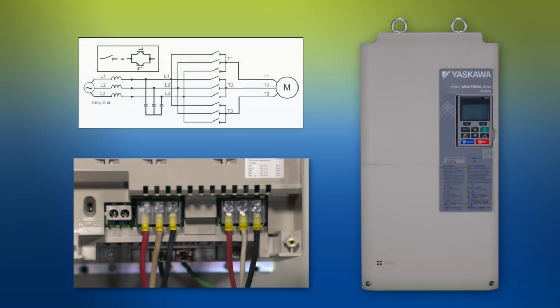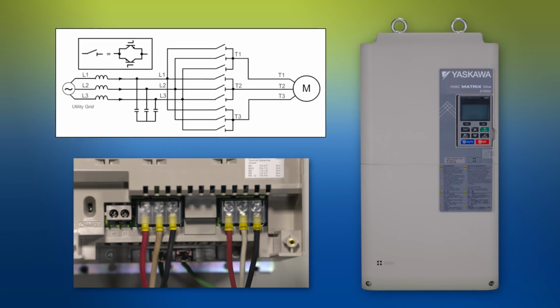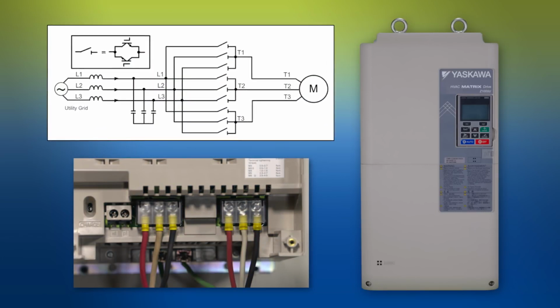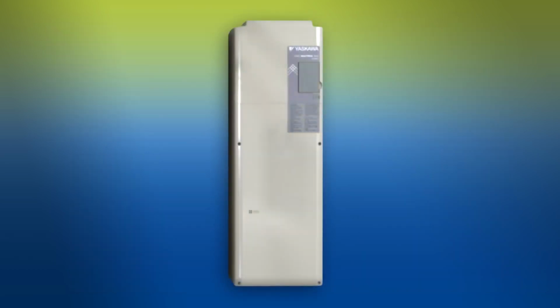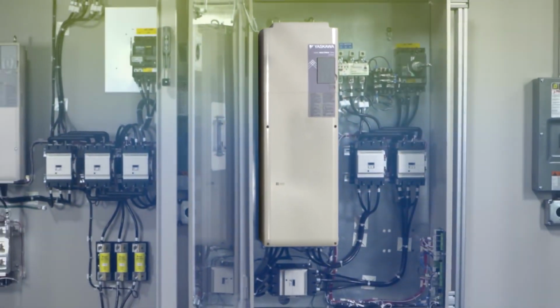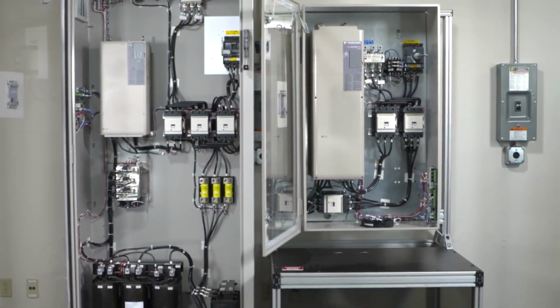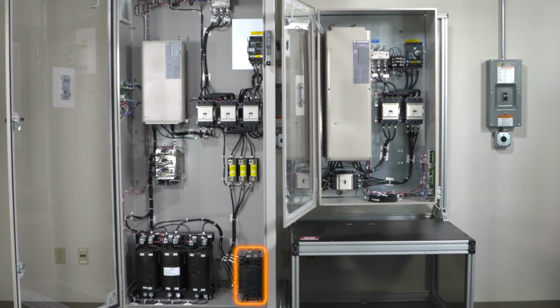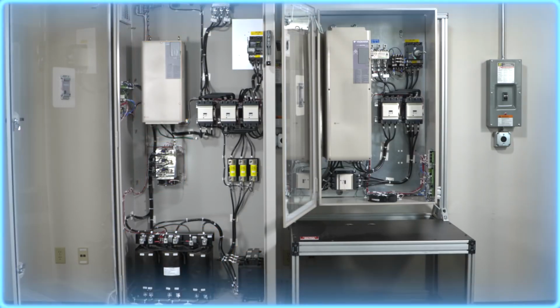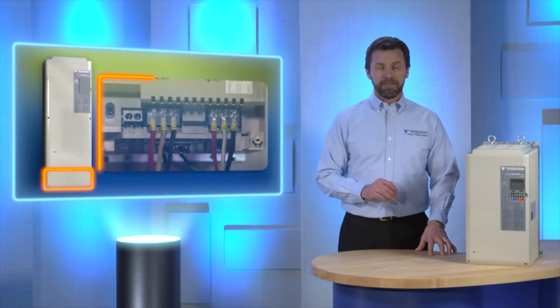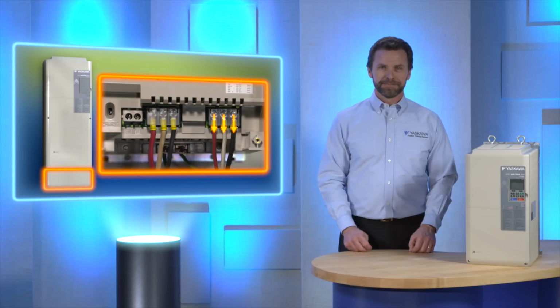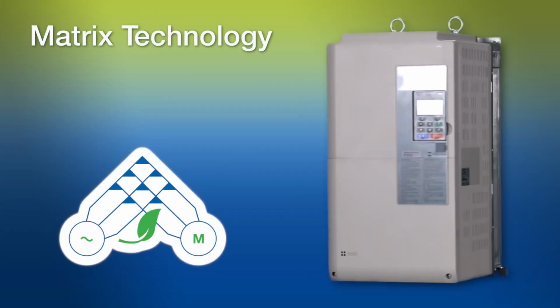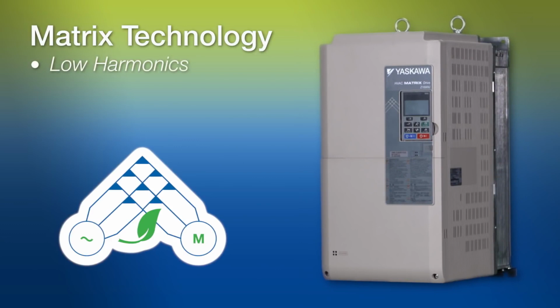The matrix drive directly converts the three-phase AC input to the variable AC output required for precise control of voltage and frequency to the motor. The matrix drive is different from general-purpose inverters because Z1000Us do not need additional external hardware, including filtering and multi-pulse configurations used to prevent harmonics. There is no DC link circuit with diodes and electrolytic capacitors. This results in a greatly simplified design: 3 wires in and 3 wires out. The key benefits of matrix technology are low harmonics, high efficiency, and serviceability.